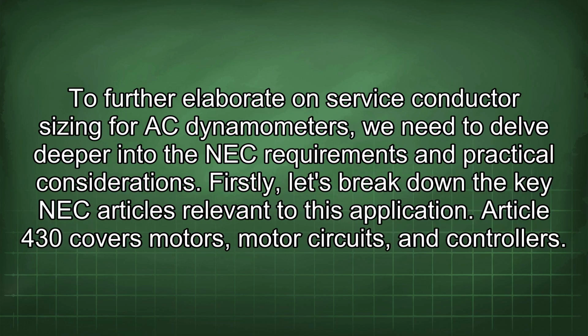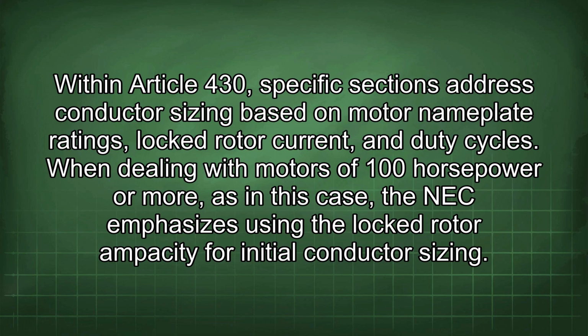To further elaborate on service conductor sizing for AC dynamometers, we need to delve deeper into the NEC requirements and practical considerations. Firstly, let's break down the key NEC articles relevant to this application. Article 430 covers motors, motor circuits, and controllers. Within Article 430, specific sections address conductor sizing based on motor nameplate ratings, locked rotor current, and duty cycles. When dealing with motors of 100 horsepower or more, as in this case, the NEC emphasizes using the locked rotor ampacity for initial conductor sizing.